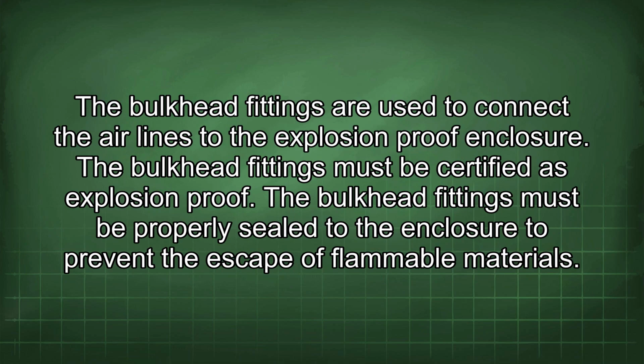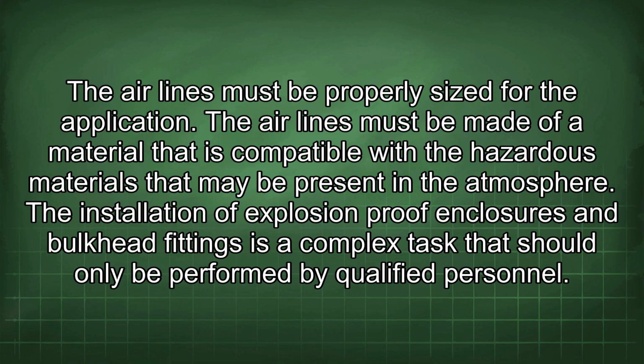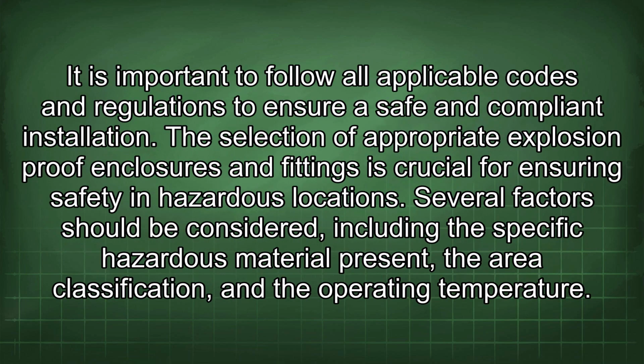The bulkhead fittings are used to connect the air lines to the explosion-proof enclosure. The bulkhead fittings must be certified as explosion-proof. The bulkhead fittings must be properly sealed to the enclosure to prevent the escape of flammable materials. The air lines must be properly sized for the application. The air lines must be made of a material that is compatible with the hazardous materials that may be present in the atmosphere. The installation of explosion-proof enclosures and bulkhead fittings is a complex task that should only be performed by qualified personnel. It is important to follow all applicable codes and regulations to ensure a safe and compliant installation.